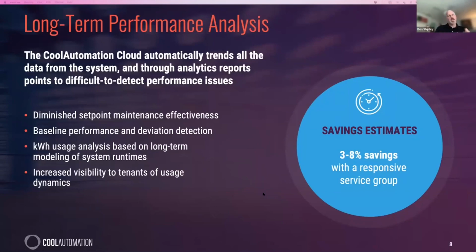With long-term performance analysis, that's completely database driven. You're going to be looking at things like diminished set point maintenance. What does that mean? It means how difficult is it for your system to get to set point, and how difficult is it to maintain that over an occupancy period. That's key - it's something you can't see day to day, or at least not very effectively, but looking at it long term, you can watch that trend start occurring.